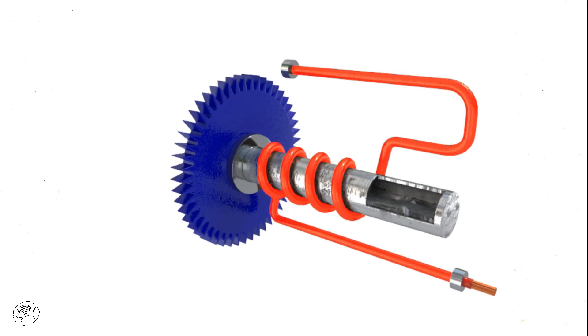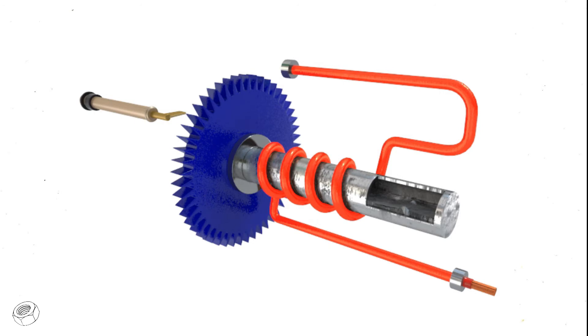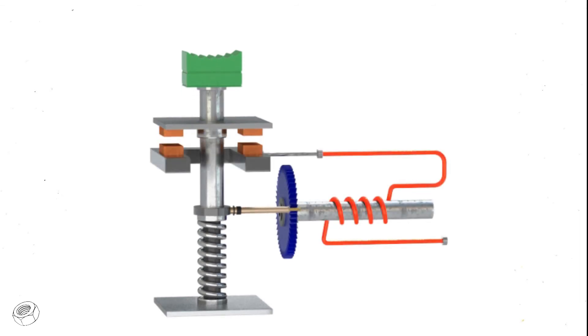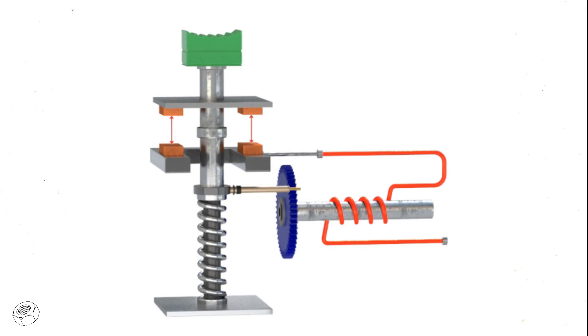When the wheel turns, it releases a pawl previously engaged in one of the cogs of the ratchet wheel. This pawl is connected to a spring-loaded contact fixture, such that when the pawl trips, the contacts automatically open and stop the current flowing to the motor starter.